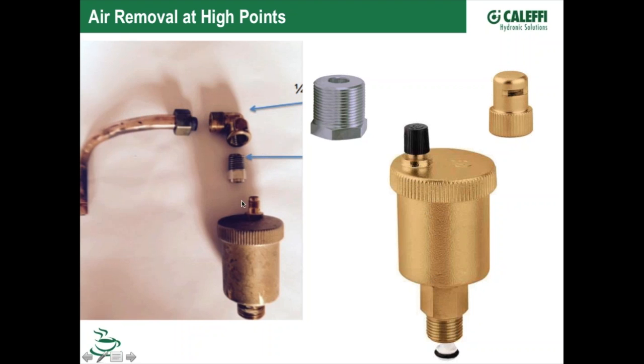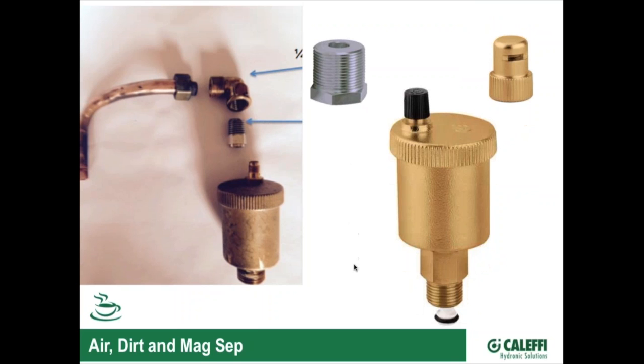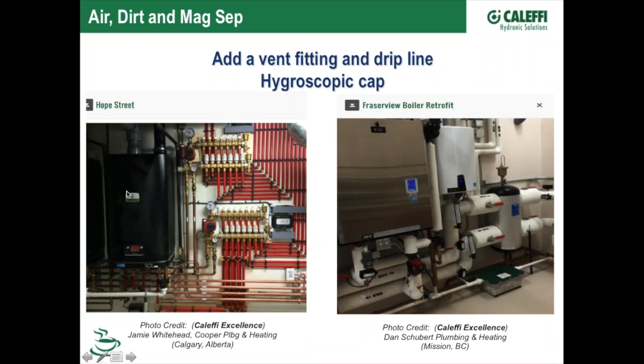We do offer this, and a lot of people don't know this. This little adapter screws onto the thread on there, and it'll turn that into a 1/4-inch MPT thread. Then in this example you can put a piece of 3/8 soft copper with a compression by FIP fitting that screws onto that transition adapter, and now you can take this vent down to the floor or out of harm's way. If you have this up in the ceiling, you can route it out to where, if this vent spits a little air or water sometime, it's not going to cause a problem. I think this shows some pictures of where they use that air vent adapter up on the top there.